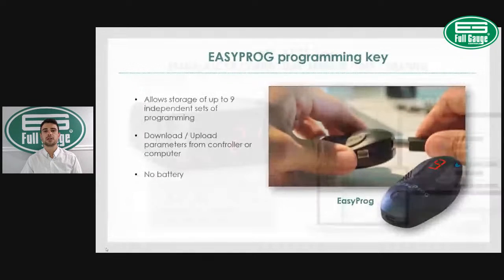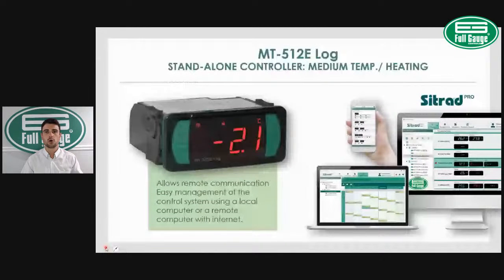We also have an option for the MT512 with remote monitoring and control. So we have a proprietary solution called Sitrad Pro software. That's the name of the software, which allows you two-way communication between the controllers and computer or cell phone, which allows you to change the control settings, retrieve historical data, or if anything goes wrong, the software sends out an alarm message so you can be alerted before the problem happens.